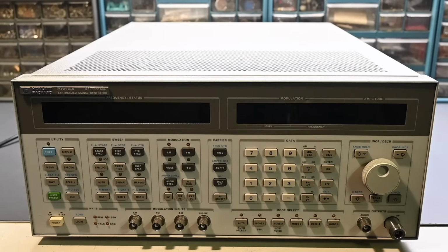The dust and kind of lint that was built up in the fan shows that the instrument probably has quite a bit of runtime on it. That's just normal, that would accumulate, but it can cause cooling issues and other problems, and it really should be cleaned up. My intent is to have this on the bench, completely working, and be able to use it in future projects, and you'll probably see it appear in future videos if we can bring it back to full working condition.